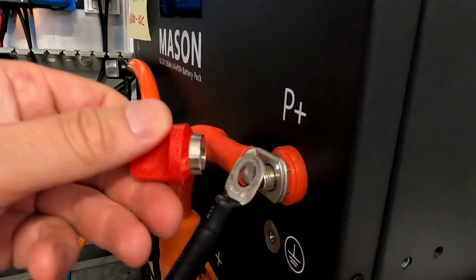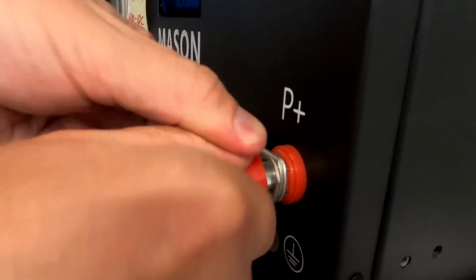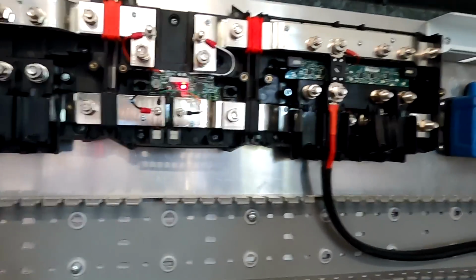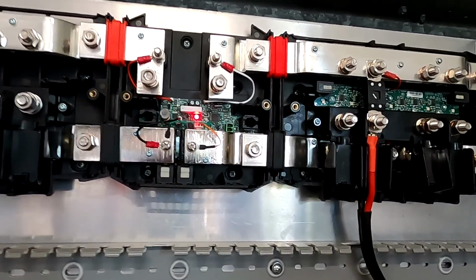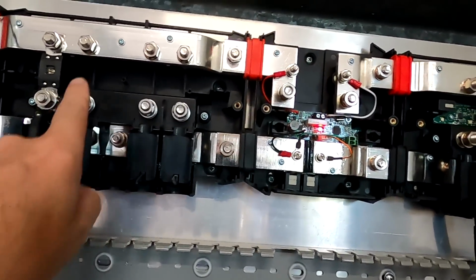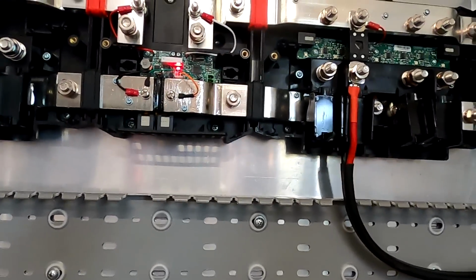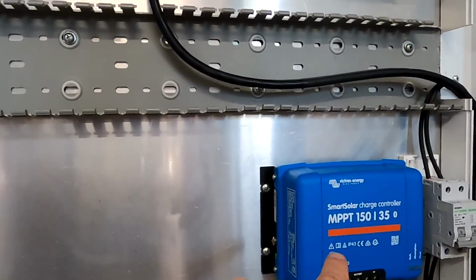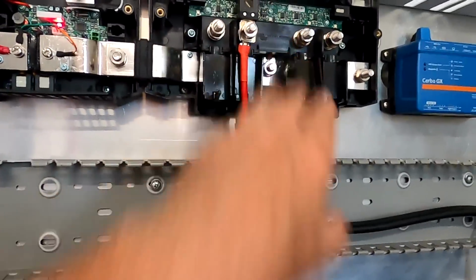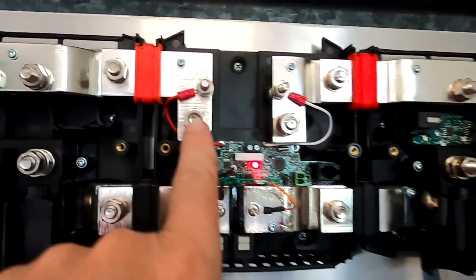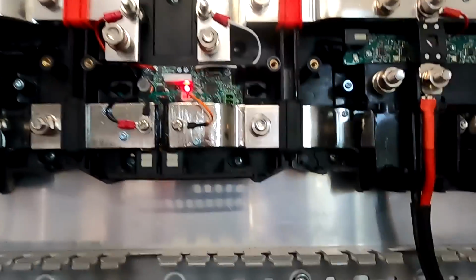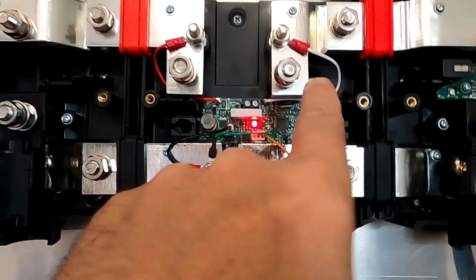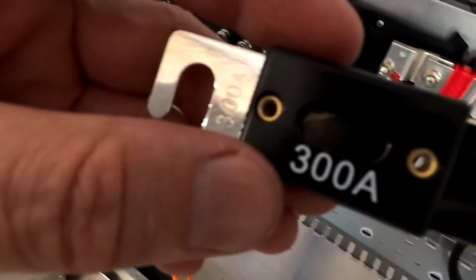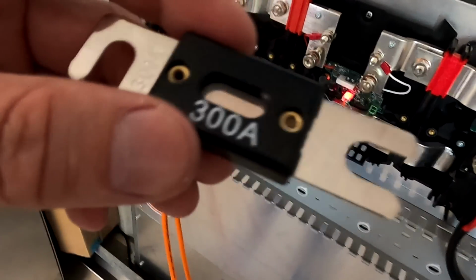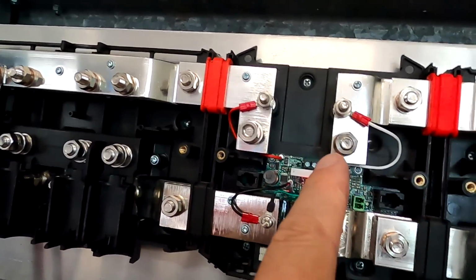There's no spark. So what we can see already is the shunt has powered up because it gets power from the battery now, but there's no connection further down to the solar charge controllers yet, to the distributor, because we haven't put in our main fuse here. So the red light means the main fuse has blown, and we just use this 300 amp ANL fuse as our main fuse in the shunt.